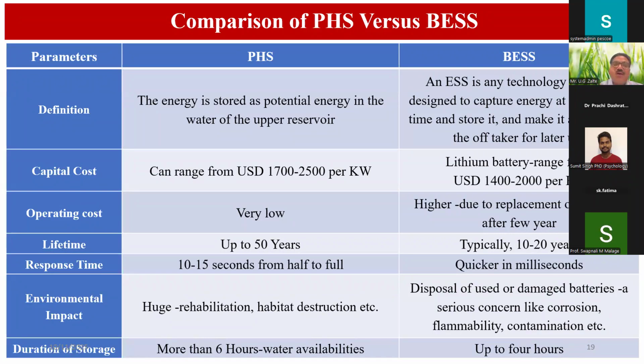The life of the pumped hydro storage can be estimated at 50 years, and it can even go beyond that. Whereas typically for the battery energy storage system, it will range from 10 to 20 years. There are various factors affecting the life of the battery energy storage system. Then the response time of the pumped hydro station ranges between 10 to 15 seconds from half to full. It's very good for grid support. And the support from the battery energy storage system is in milliseconds only, much faster than the pumped hydro stations.